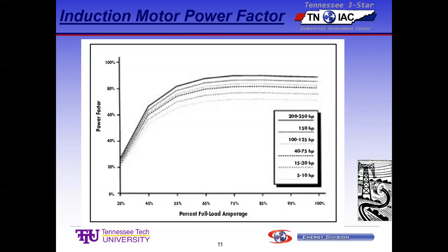But most motors are sized a little bit bigger than the load. If I'm buying a motor for a pump and I figure the maximum horsepower that pump is going to need is 28, I'm going to put a 30 or 40 horse motor on it to make sure I don't overload the motor. And then when they turn it on, maybe it actually needs 22. So I've got a 30 horse motor or a 40 horse motor actually pulling 22 horsepower. It's only about 50 to 60% loaded, which puts you back in, there's 50% load, there's 75% load. So you see, as the load goes down, we see the power factor fall off, okay?